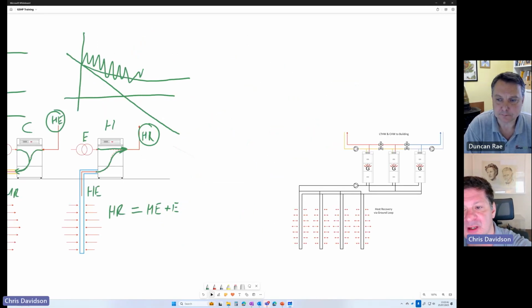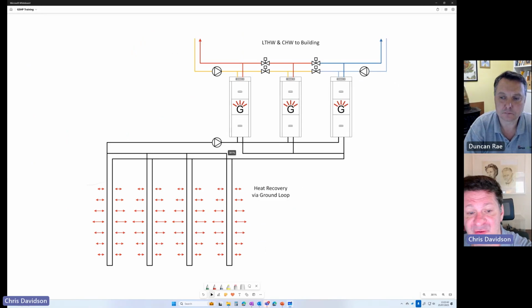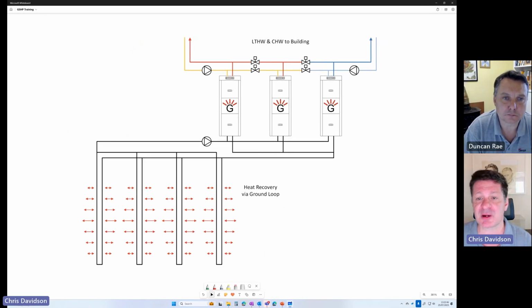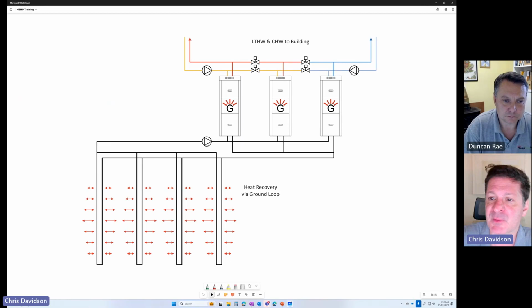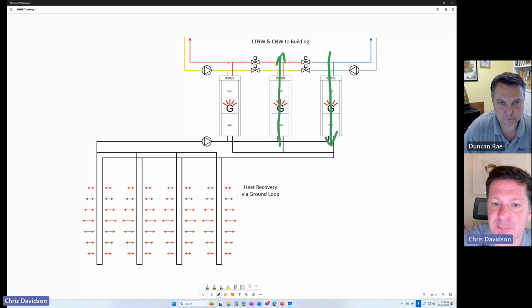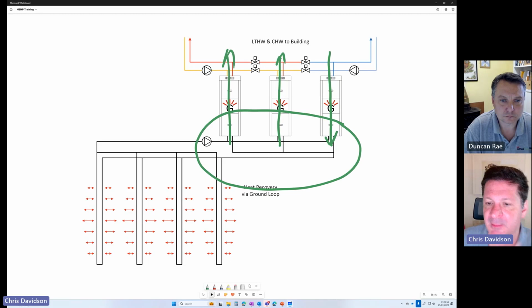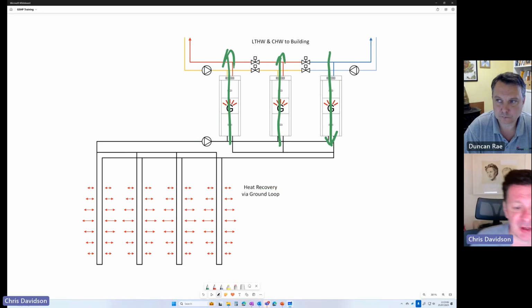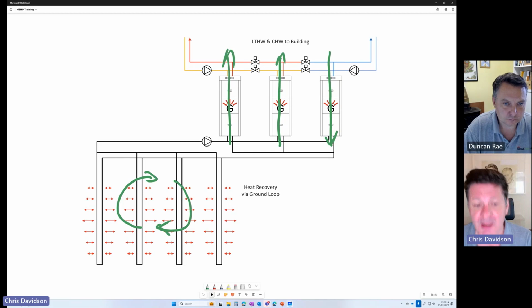So let's look at how we apply this, let's start with a commercial building. In this commercial building, we've got heating and cooling going on. So the cooling heat pump here is taking heat from the building and putting it into the ground. And we've got a couple of heat pumps here, then heating. So right away, you can see we've got energy recovery going on in that ground loop. Now, there's quite a number of systems that can do that energy recovery instantaneously, but the real magic of ground source is we can actually do that heat recovery interseasonally. So we can put heat into the ground in the summer and get that heat back out in the winter.